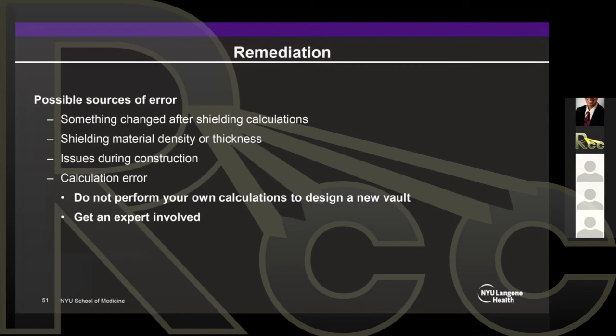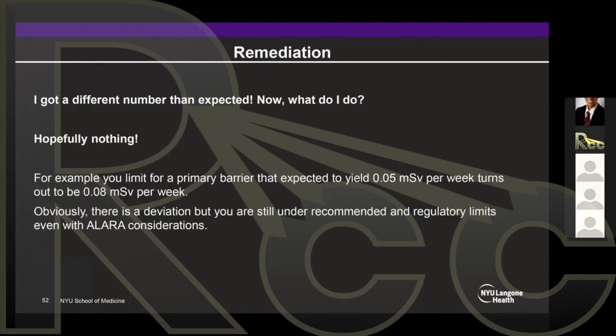So what are possible sources of error? Maybe something changed after the shielding calculations, right? Your isocenter got moved or something happened there. Shielding material density or thickness, issues during construction, calculation error. And again, just to reiterate, always look for advice when doing calculations for a new bunker. Get an expert to do it or get involved with you in doing it. So I got a different number than expected. Now what do I do?